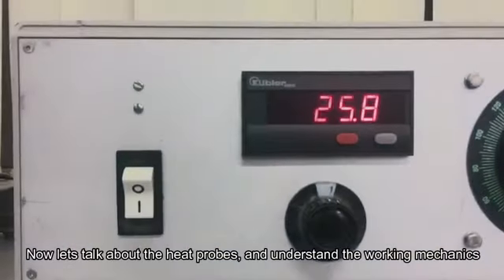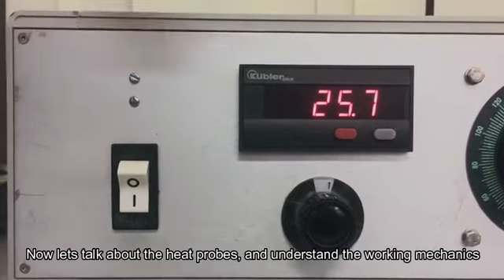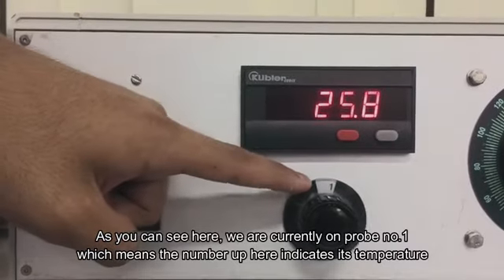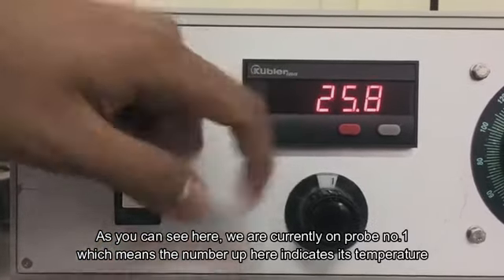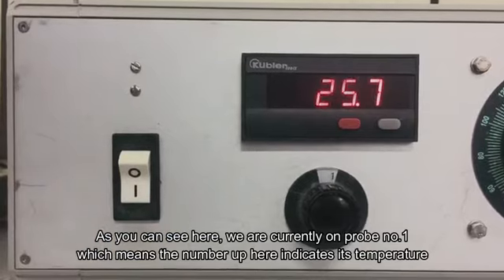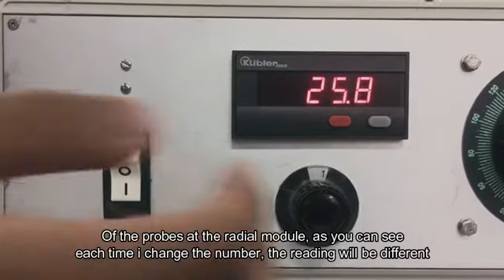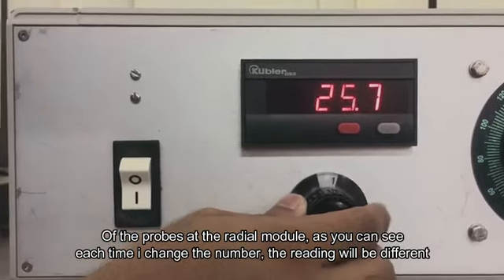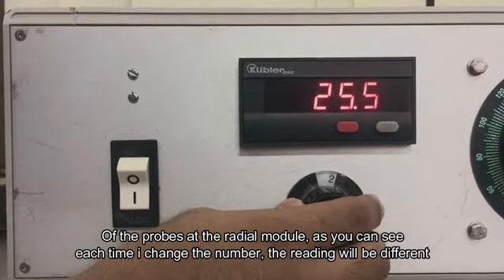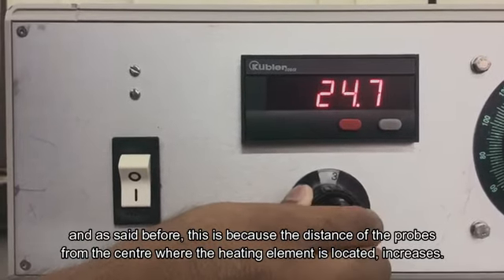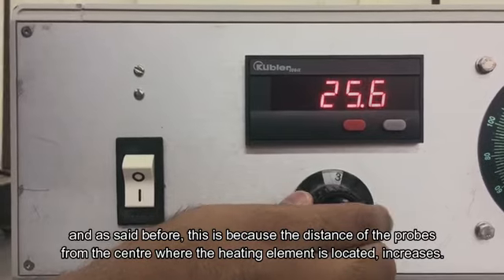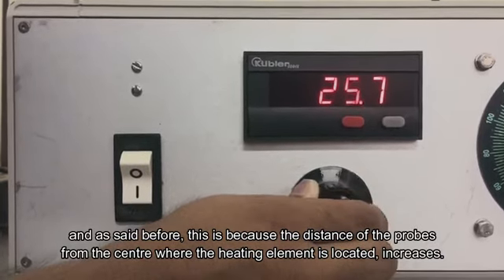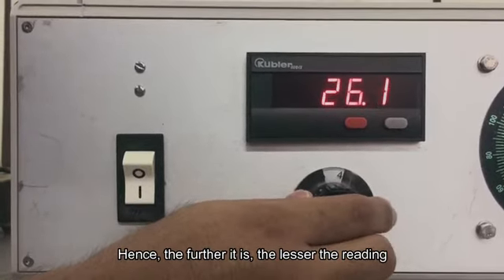Now let's talk about the heat probes and understand the working mechanics. As you can see here, we are currently on probe number 1, which means the temperature up here indicates the temperature of the probe at the radial module. Each time I change the number, the reading will be different. And as I said before, this is because the distance of the probes from the center where the heating element is located increases. Hence, the further it is, the lesser the reading.